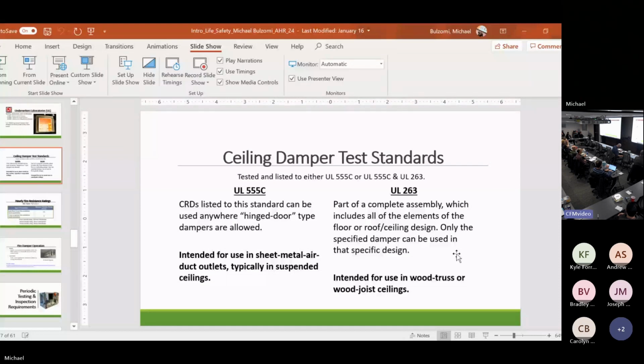I'm going to run out of time doing this. Do we kind of understand that a little bit? And when you're approving submittals for multifamily, do you consider that? Do you look at the UL listing, let's say it's a P554, pull the P554 listing and look at the damper manufacturers, and then go back to the contractor and say, sorry, only Ruskin is approved for this, I can't accept that? Okay.